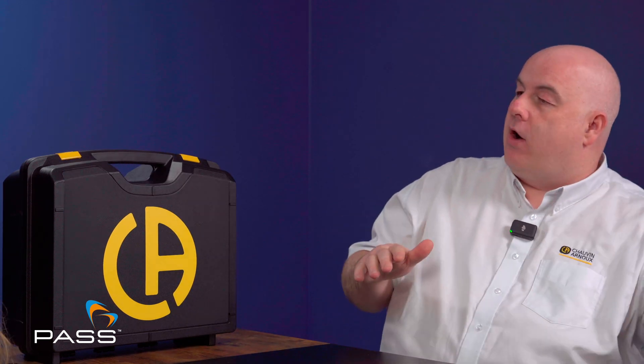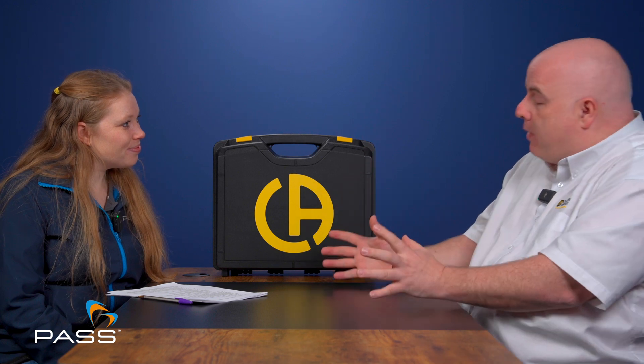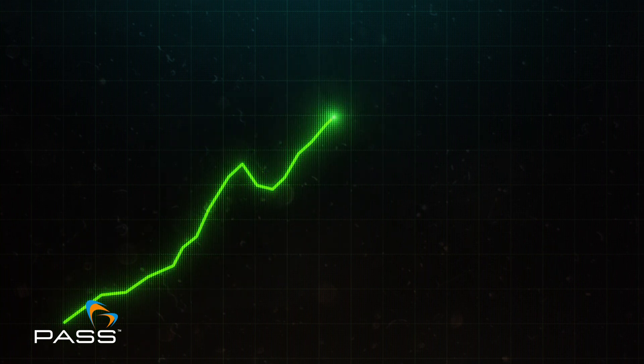How are PELs different from power quality analyzers? Generally, a power and energy logger monitors what we call trends — things occurring over a longer period of time. Whereas a power quality analyzer is generally looking for faster events like spikes and surges within an installation. The power and energy logger doesn't really look at very fast events; it's looking for trends over a longer period of time.